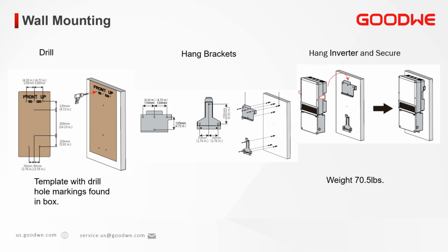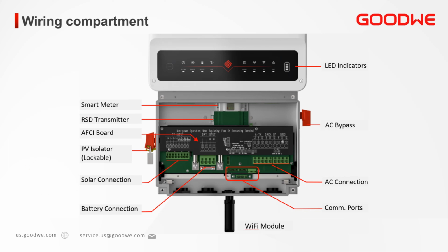Use the included cardboard template to mark for the holes for mounting the inverter hanger plate. Also make sure to select the correct hardware for the type of wall and the weight of the inverter. This inverter can weigh up to 70 pounds. Before we jump in depth of the installation, let me give you a general orientation of the inverter.